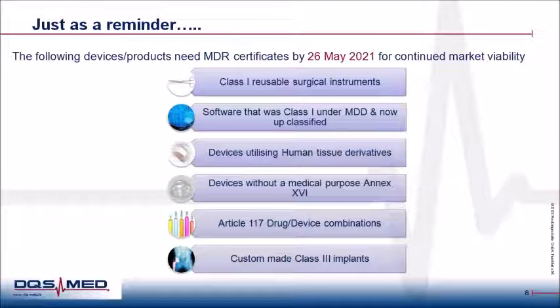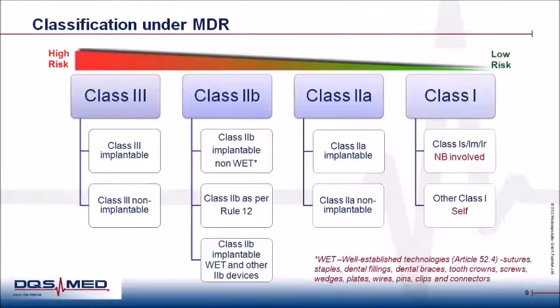So, as I mentioned, the classification of MDR is pretty much the same as it is currently under the Medical Device Directive. The Medical Device Regulation has 4 main categories of medical devices, namely Class 1, Class 2A, 2B, and Class 3. This goes from products with low risk, that is Class 1, to products with high risk, that is Class 3. The only difference, which is not yet available in the current medical device directive, is Class 2B devices as per Rule 12. I'll come to it in a later part of the slide.